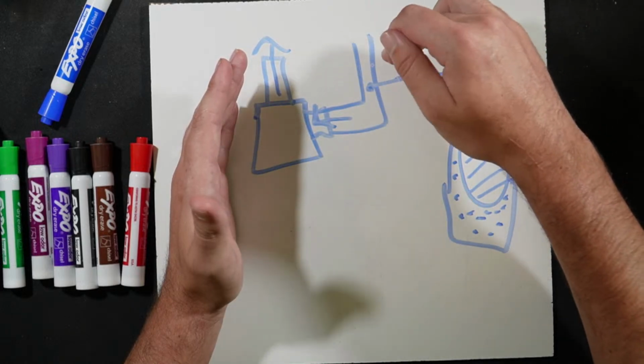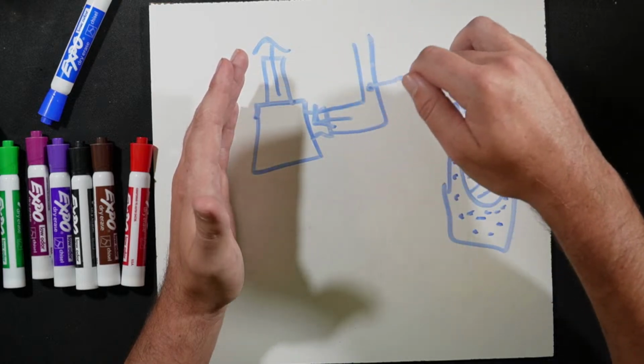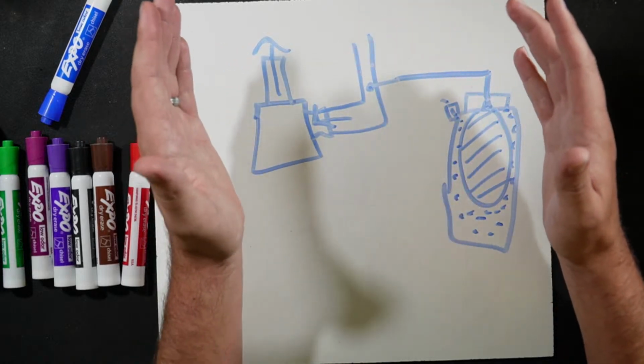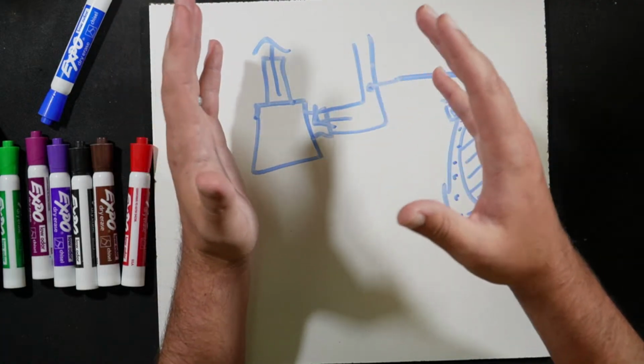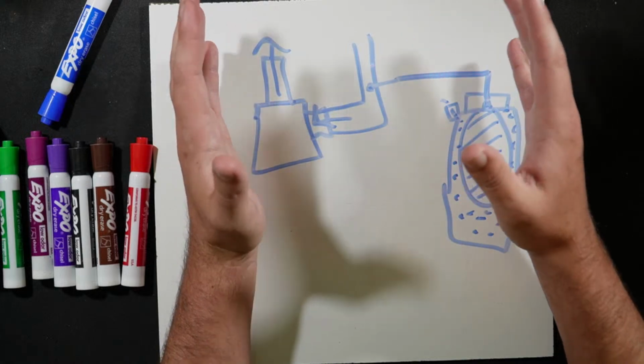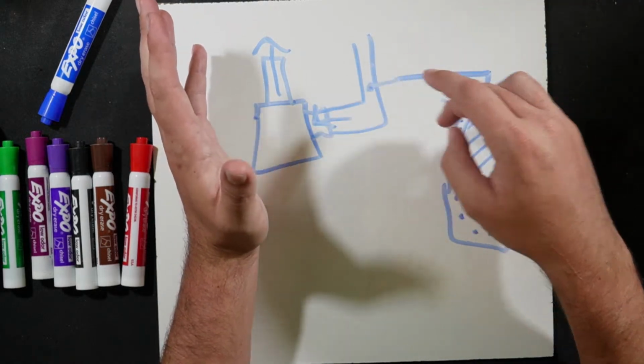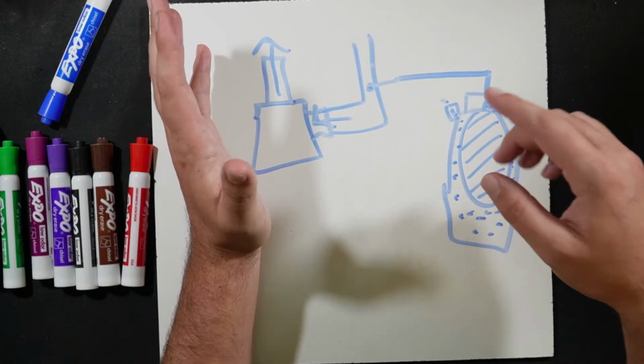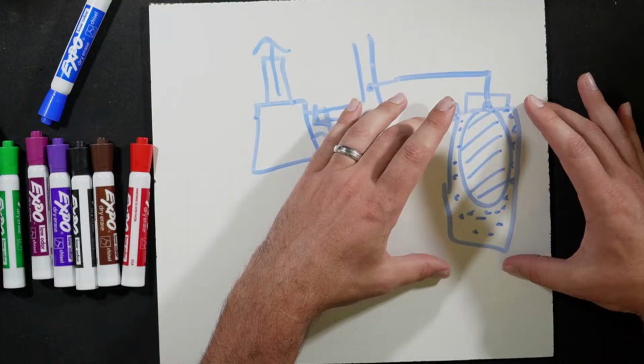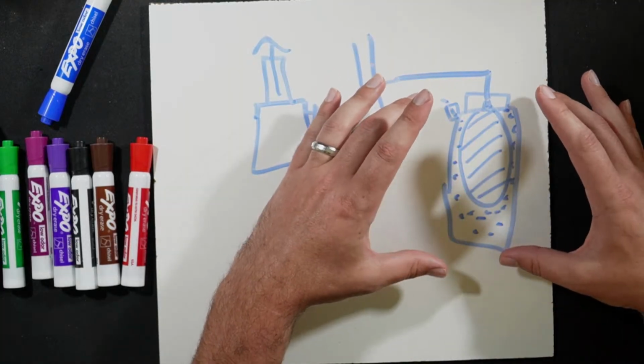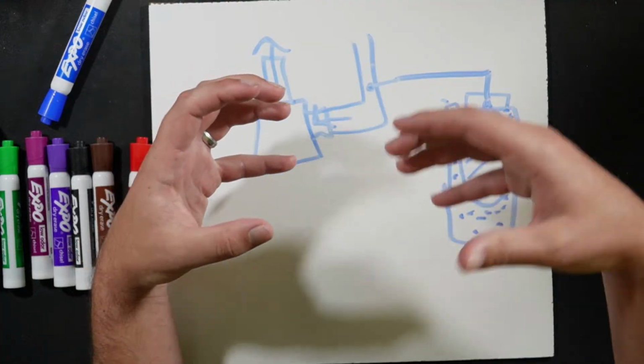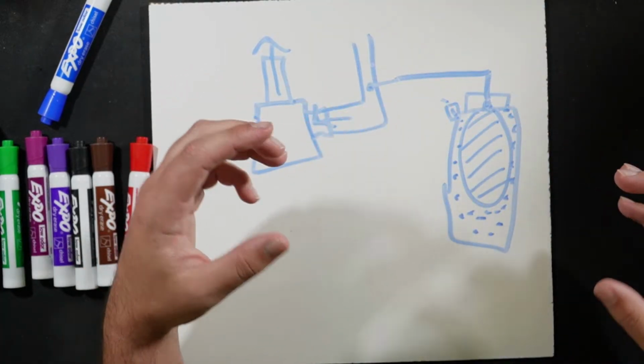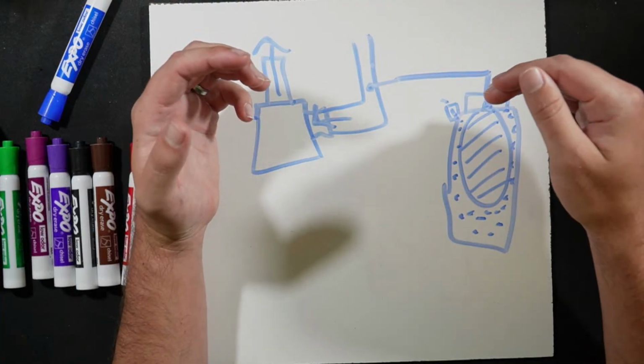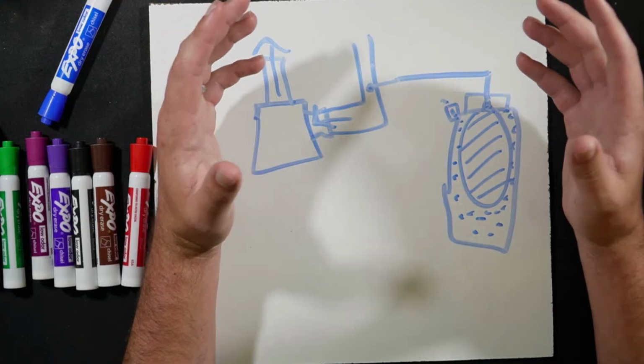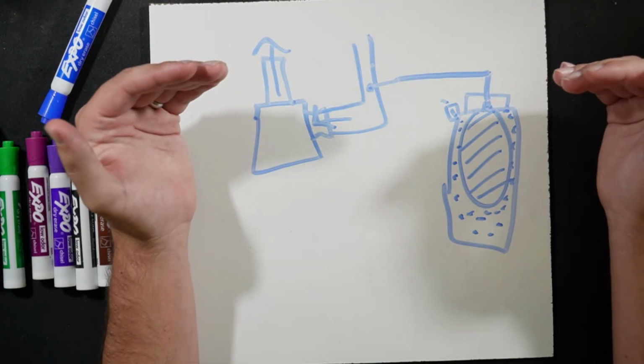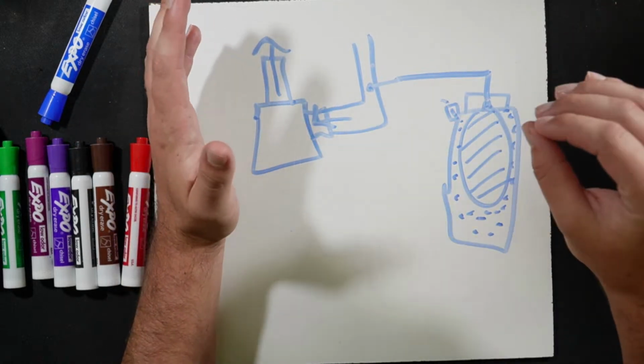In that state, I would prefer to be in the 50s range right here. So if I was at least 52 or 53 on my incoming water, that would be close enough, in my opinion. You're within a couple of degrees to then set this tank pressure. The reason for that is you want this tank calibrated to your operating conditions, and then allow the off cycle, when it heats up, to expand out further from there as needed. That is my personal preference, and to my understanding it is the best way to go about it. That's the way I've been trained to do it, is more of what I'm trying to say.